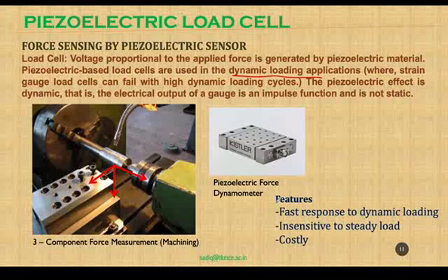The features of these piezoelectric load cells are that they have fast response to dynamic loading, and the negative side is that they are insensitive to steady load. That means piezoelectric load cells are not suggested for static load, as we see in the case of just weighing. That is static load, when there is no changing load. That happens in the case of weighing machines and all. These are very costly compared to strain gauges.